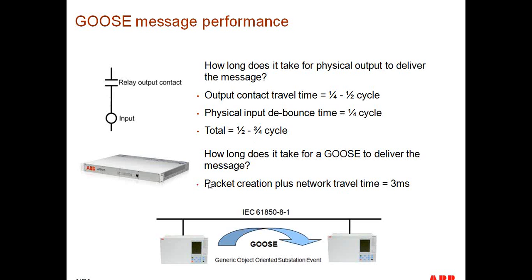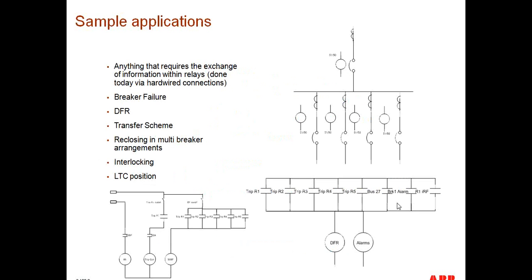Since GOOSE messages are properly structured Ethernet packages that have checksums associated with them, there are no transient concerns at that point. There's no way that a transient could modify the Ethernet packet and then in turn be wrongly interpreted by a receiving device, since there are checksums that protect devices from that.